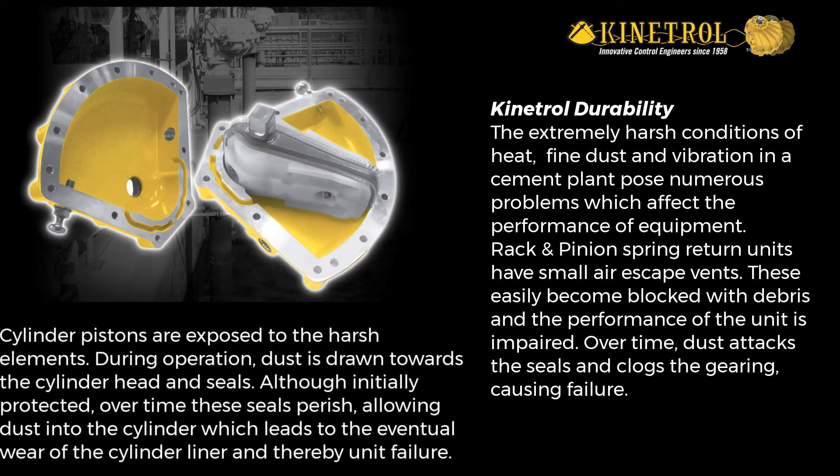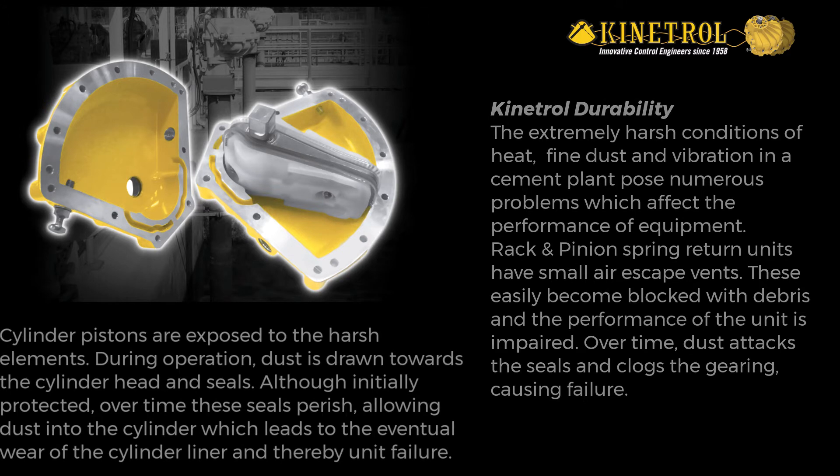Cylinder pistons are exposed to the harsh elements. During operation, dust is drawn towards the cylinder head and seals. Although initially protected, over time these seals perish, allowing dust into the cylinder, which leads to the eventual wear of the cylinder liner and thereby unit failure.